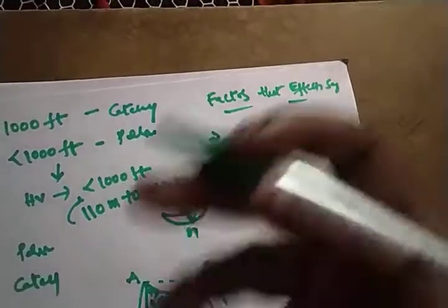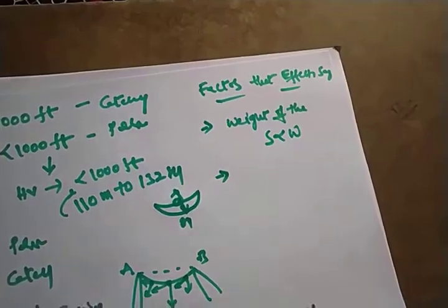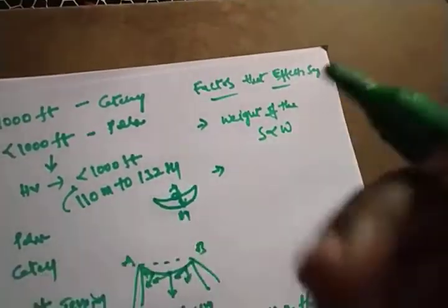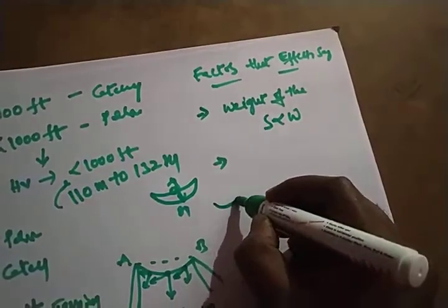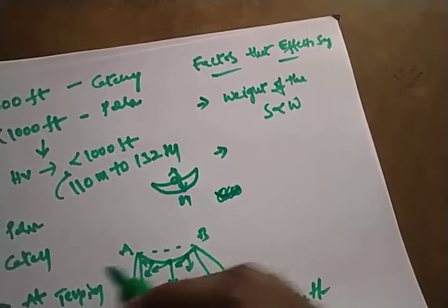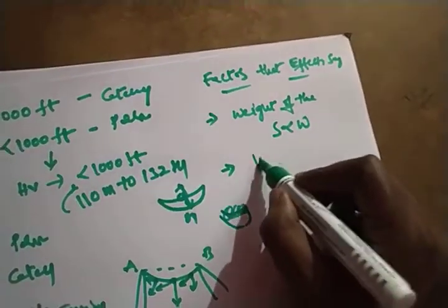Due to climatic conditions, countries like Canada and Norway are very cold, ice falling countries. When a transmission line is placed in those areas, the ice will surround the transmission line itself. So the weight of the conductor also increases, then the sag will increase. The sag also depends on the location of the conductor.